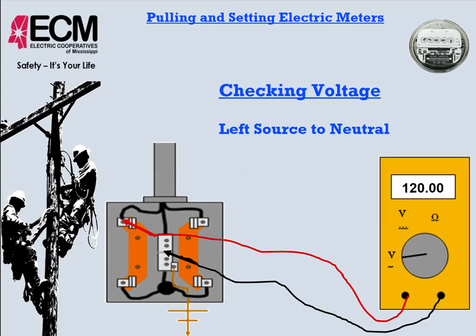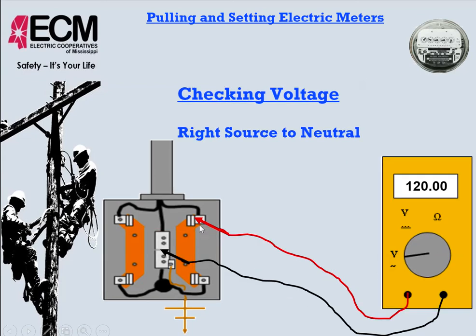So one of the first checks that we want to make is that we want to put our voltmeter, our red hot lead, on the line side lug and what we assume to be the neutral, and we should get 120 volts. But right then we don't know which one of these is hot. Okay, so we want to check the other side and make sure that we get 120 volts there as well. So we know that now this is our left side line side, from there to ground is 120, and our right side from the line side to the ground is 120.